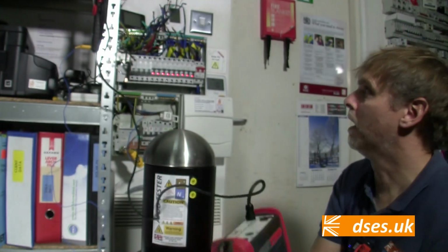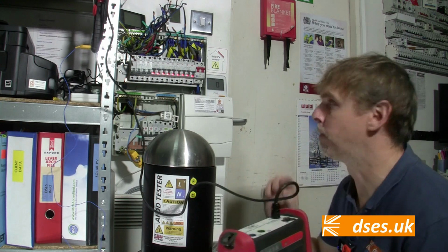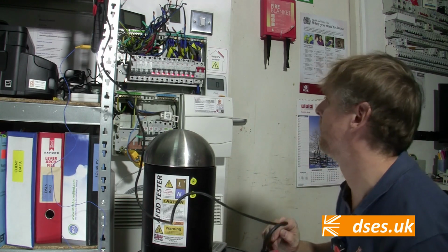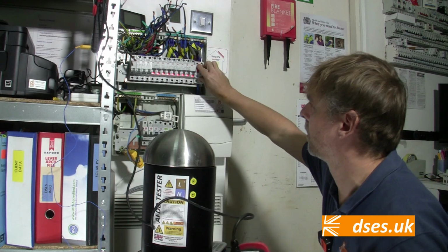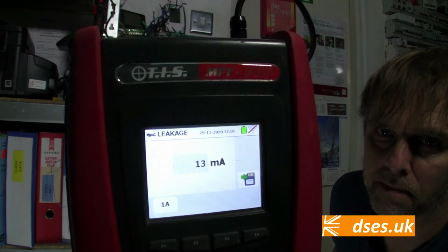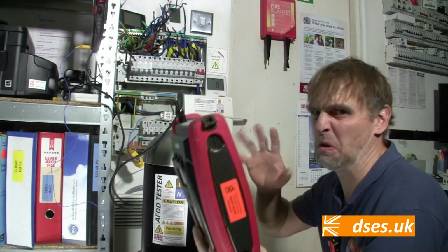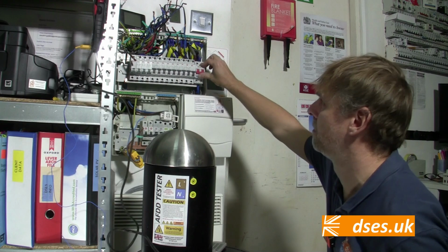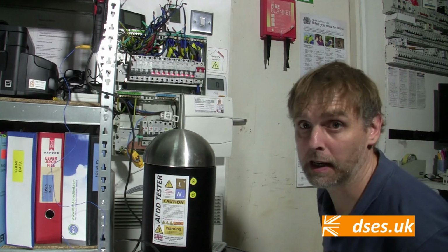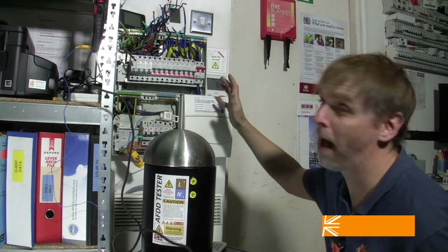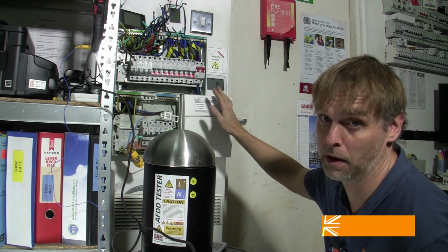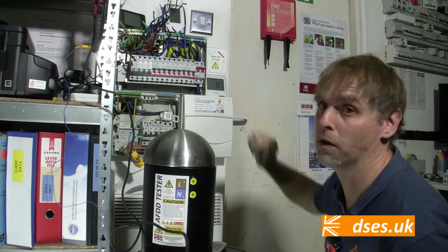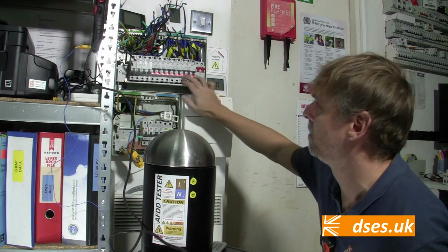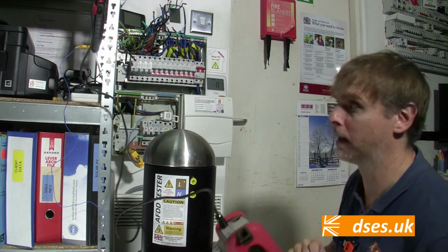Now, the only place I can get my clamp on is before the smart meter, so the smart meter is going to be taking a bit. So let's turn that off, and we drop to 13 milliamps. So we'll call it about 30 milliamps that these are taking when they're just there, switched on, not doing anything, the circuit's dormant. You're losing about 30 milliamps for these 9 devices being on.